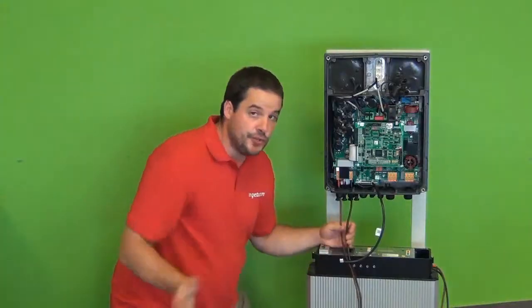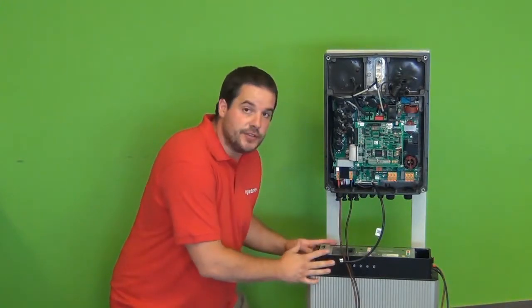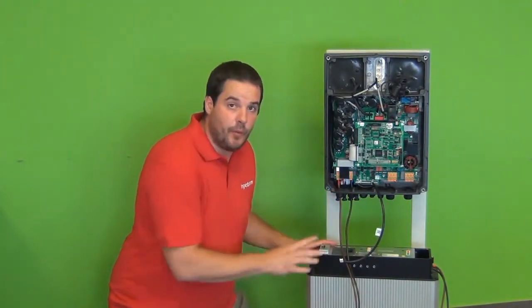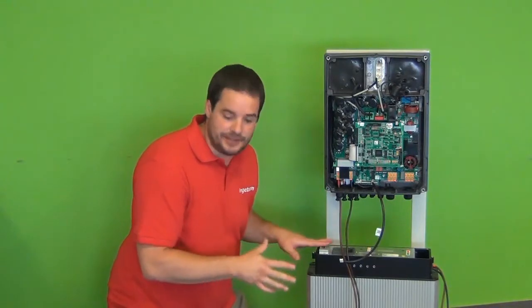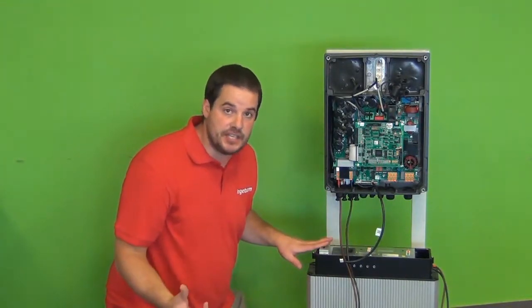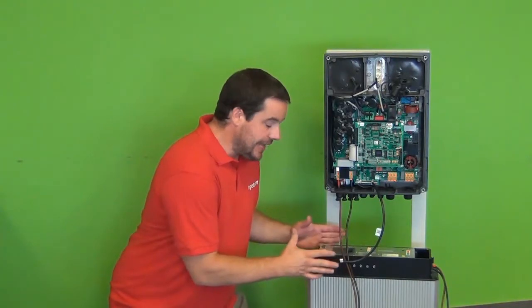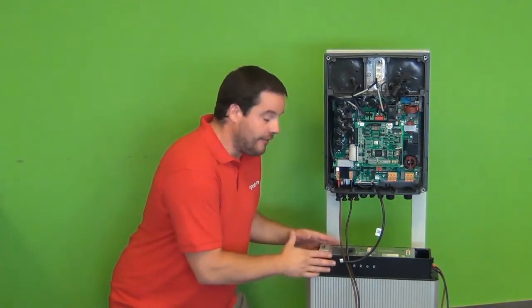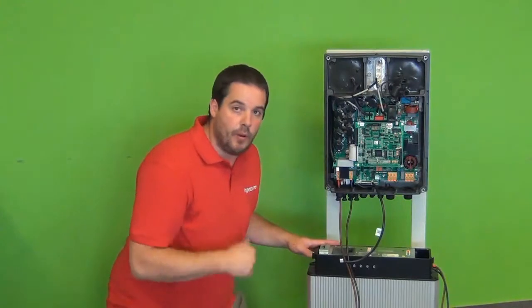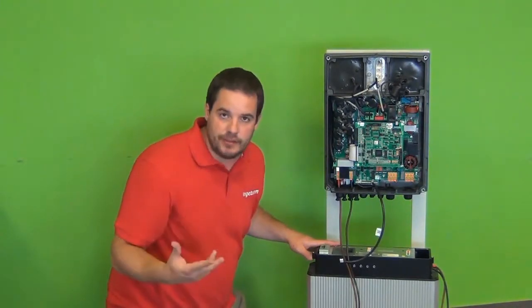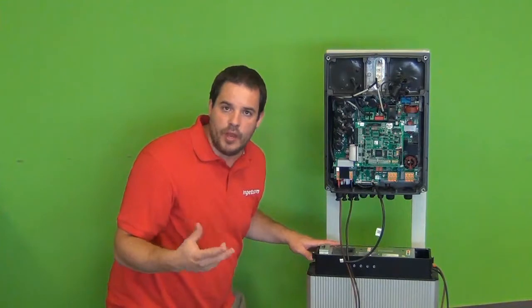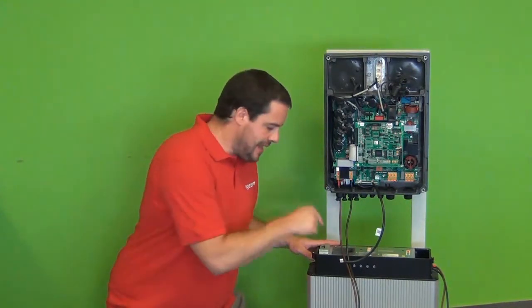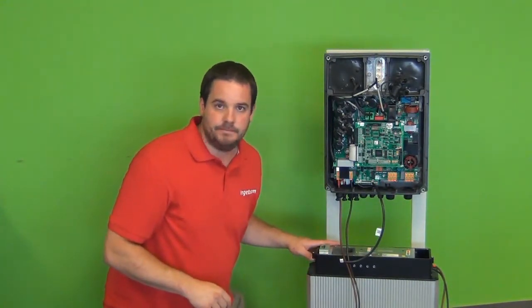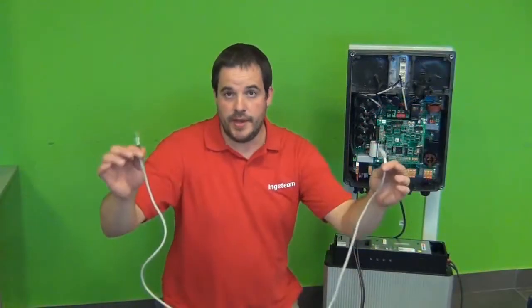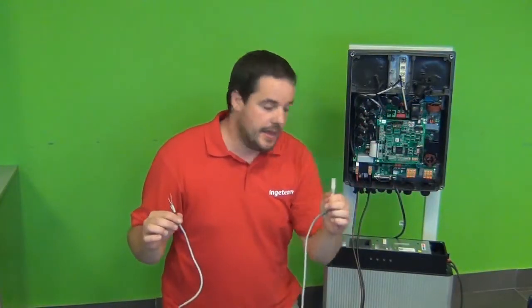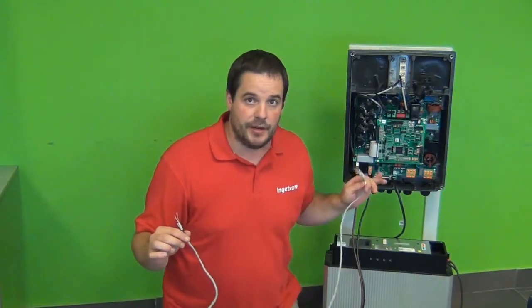The next thing I have to do is to actually connect the communications from the battery to the inverter. Why? Because this is a lithium-ion battery. So there's a BMS system that actually is telling at all times what's the state of charge of the battery to the inverter. So when the inverter makes all the algorithms, or when the INGECON SUN EMS board is doing all the calculations, it takes that information from the battery, right? I'm gonna use this communications cable to communicate the BMS from the battery with the inverter, all right?